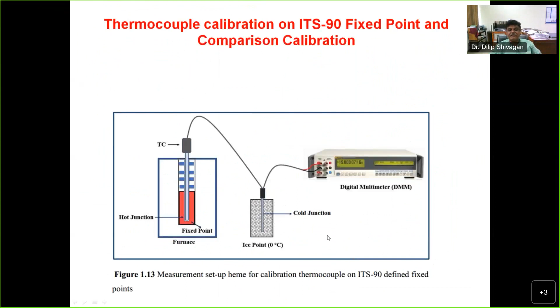We have the facility up to 1600, and there are still requirements for a very high range. The reference junction which you have at the ice point needs to always be at the ice point if you want the absolute measurement. If it is at room temperature, which is practically the case in site calibrations also, you have to correct this value with respect to the total EMF. You see the standard table, you go from 0 to say 24 or 25, and you add this EMF there. As I said, inhomogeneity is a very dominating factor. You can see it in a very stable furnace.